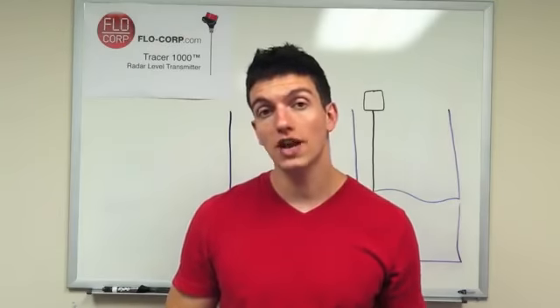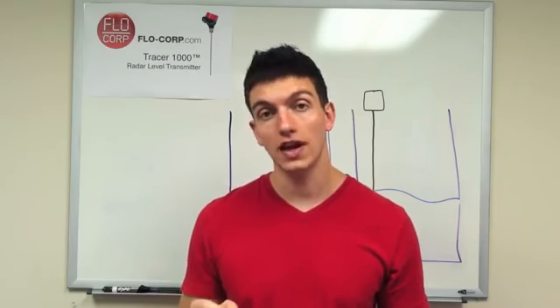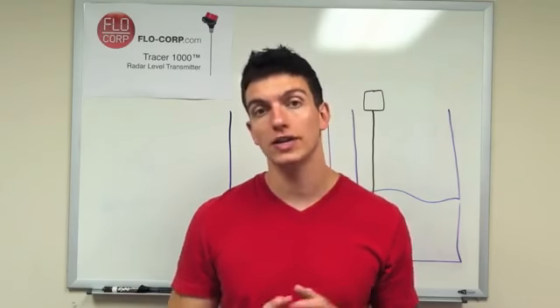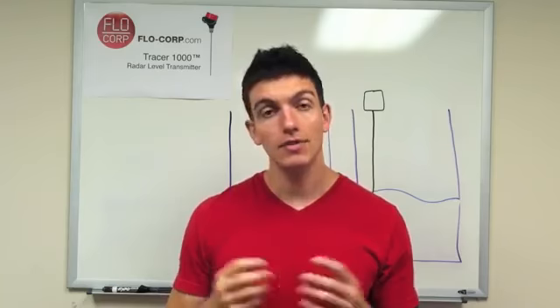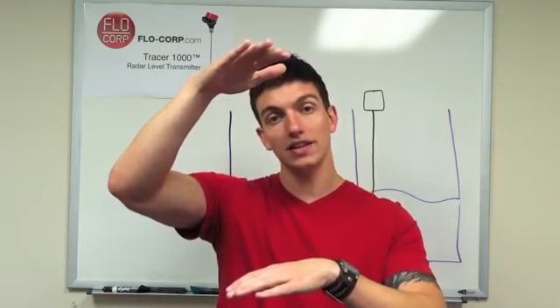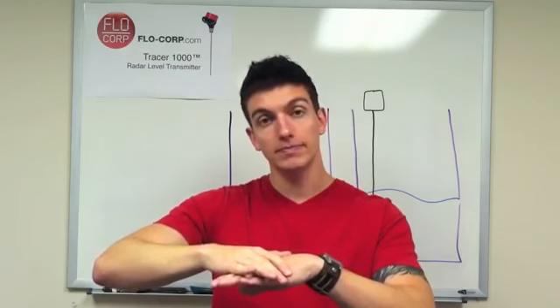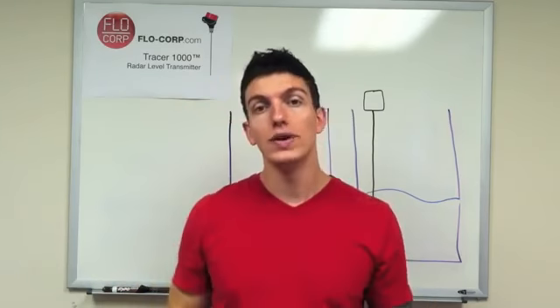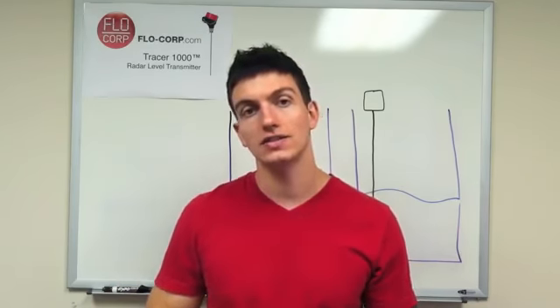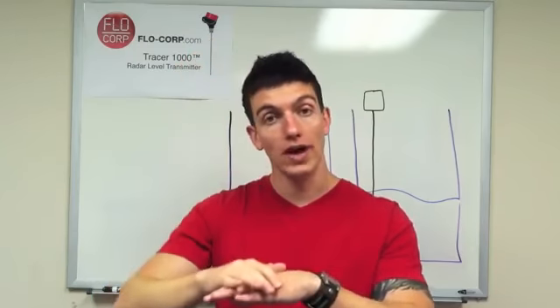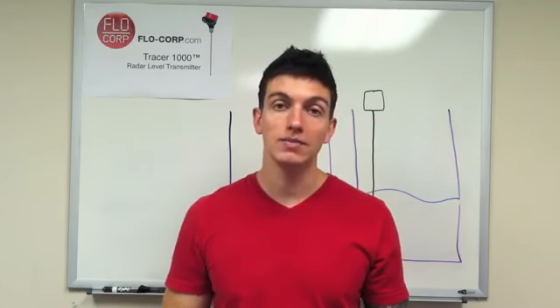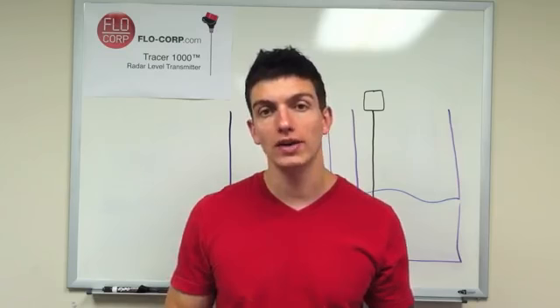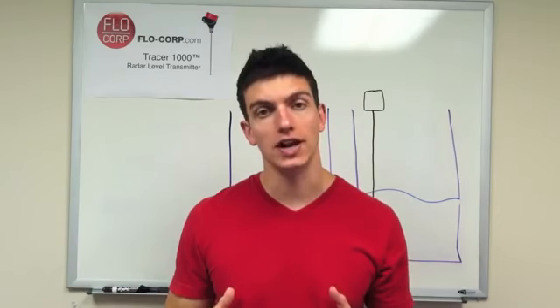There's a principle called time of flight that both ultrasonic level meters and radar level meters operate on. Time of flight tells us that if we send a signal from the driver to the surface of whatever we're measuring and it returns, we can divide that in half to get the time for the signal to travel one way. Once we have the one-way travel time, we can get a level calculation out of that.